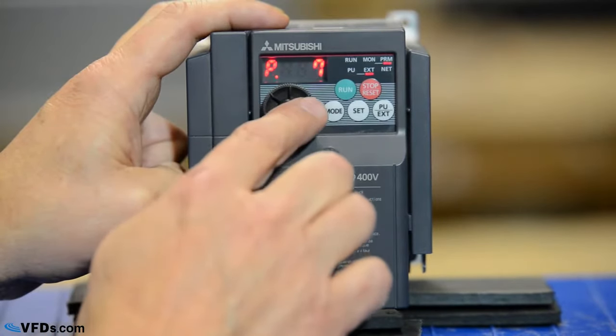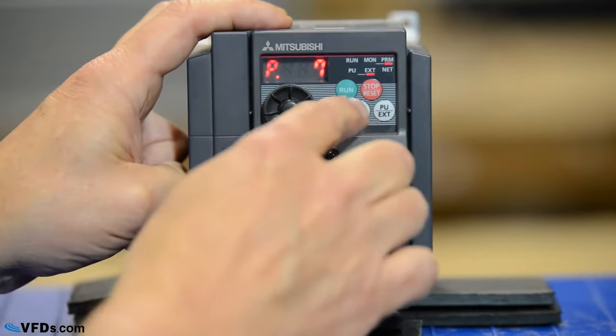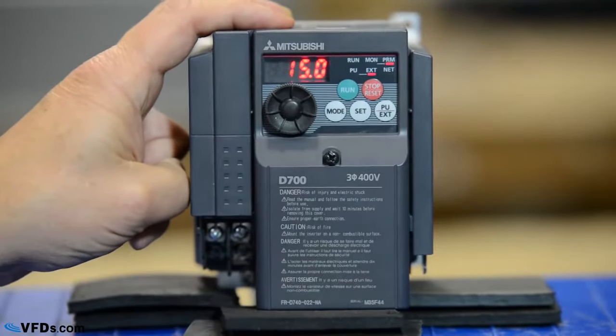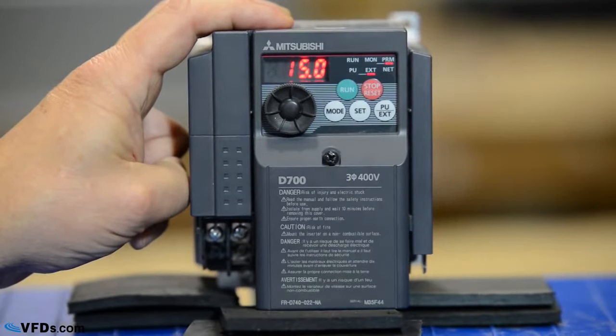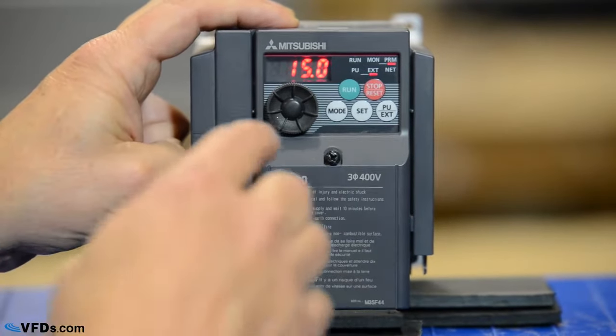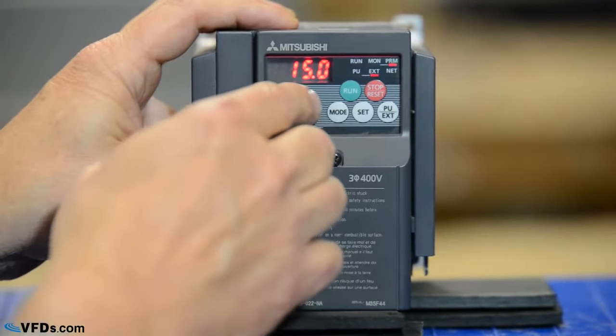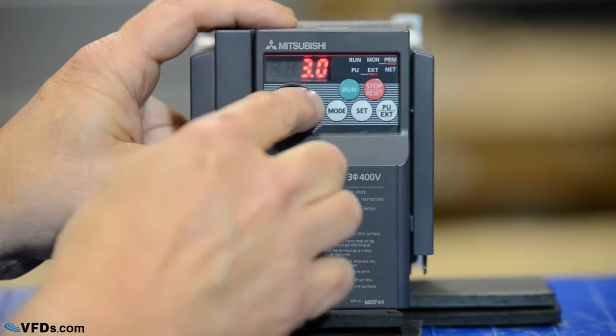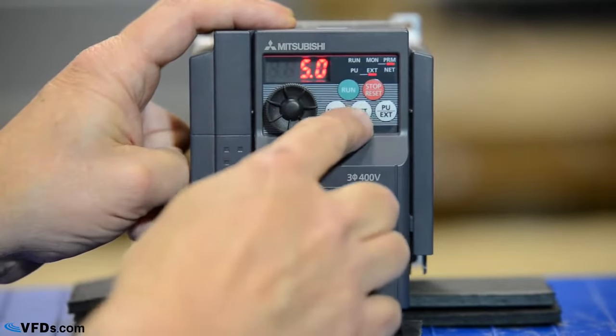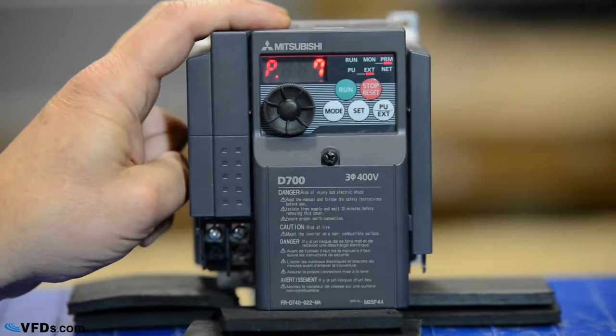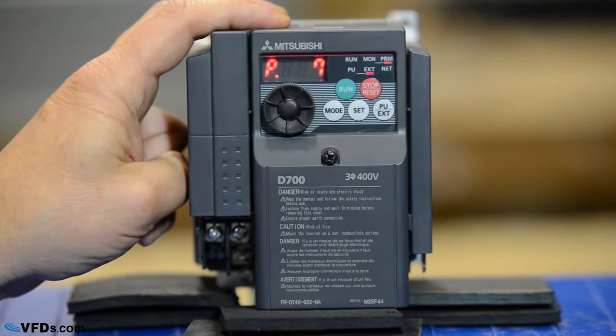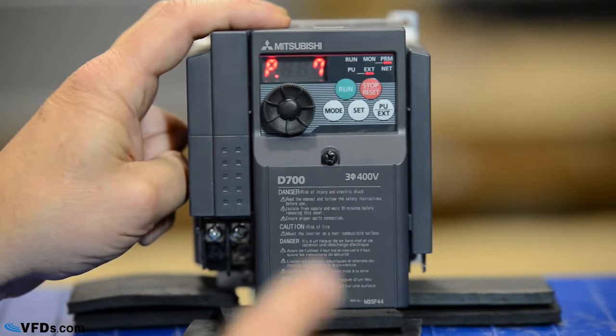Now let's go to parameter 7. This is the drive acceleration time. I push set and my acceleration time is 15 seconds. I'd like this small motor to accelerate in 5 seconds, so I'll change that to 5 seconds. Press set and now it will accelerate from 0 to 60 hertz in 5 seconds.